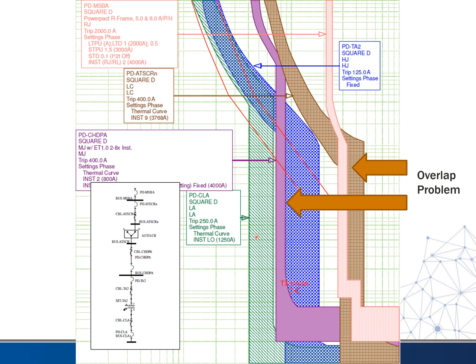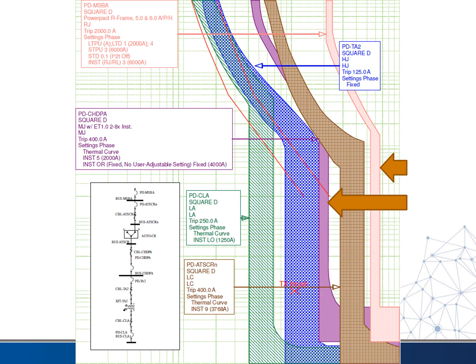When I change the next slide, you can see the pink one and purple one move. Notice where they are, kind of in the mix of things — and then on the next slide after adjustment, you can see the pink one was pulled back and the purple one was pulled back. There's still a little bit of overlap between the purple and the brown breaker, and between the green and the blue, but that's not uncommon — you can't always get rid of all the overlap, but you can make it as good a situation as possible. The overlap is now better coordinated.